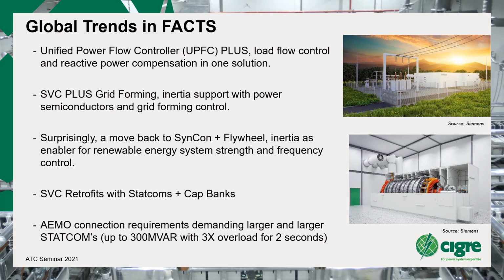Surprisingly, there's a move back to synchronous condensers and flywheels, because inertia is an enabler for renewable energy system strength and frequency control, and has allowed South Australia to increase its exports and reach higher levels of PV being responsible for generation within that state.